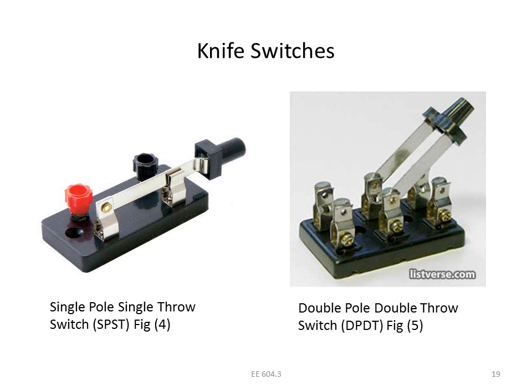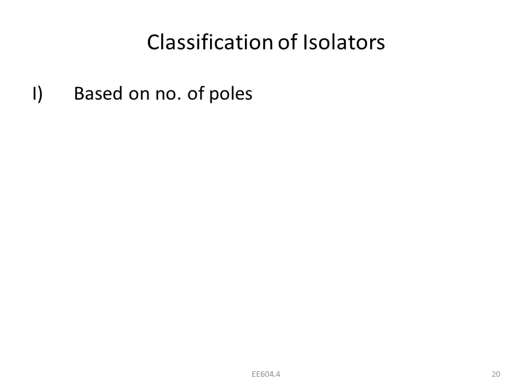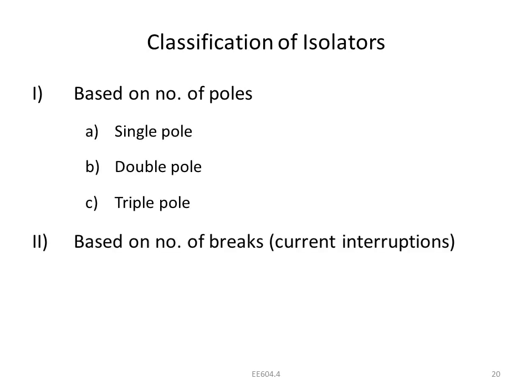It does not operate under load condition. If it is operated under load, a spark and arc formation will be there and make huge damage. It is not specified for breaking and making capacity. The classification of the isolator is based upon the number of poles: single pole, double pole, triple pole. Based upon the number of breaks, for current interruption, it will be a single break isolator or a double break isolator.